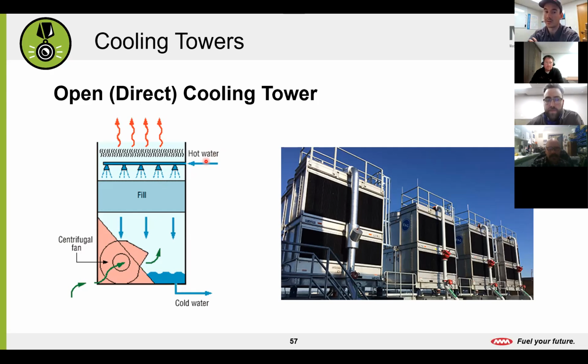They're extremely dirty, but they're easy to install. They're the cheapest upfront cost. They're very efficient though, because you don't have any intermediate heat exchangers to try to reject heat through. It's just direct hot water to the outside air, loses its heat, goes back into the building. But the downside is the cleaning of it. To me personally, I don't like them too much. I like a closed style cooling tower, for the guy that's got to clean it.